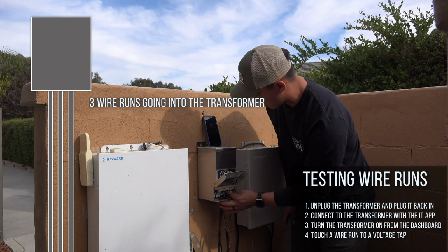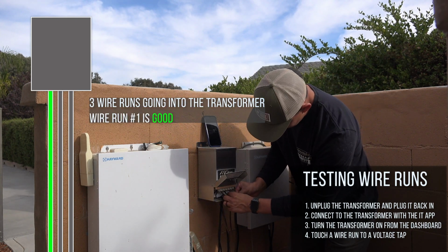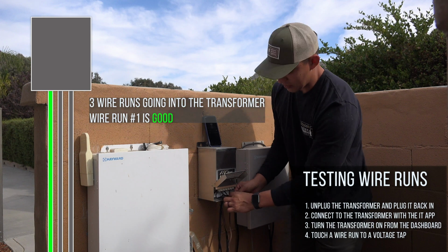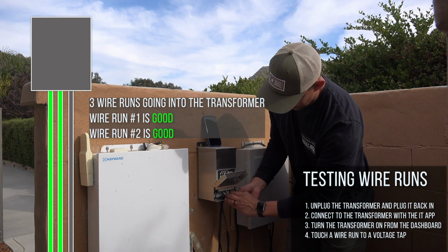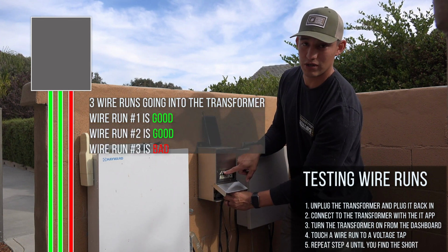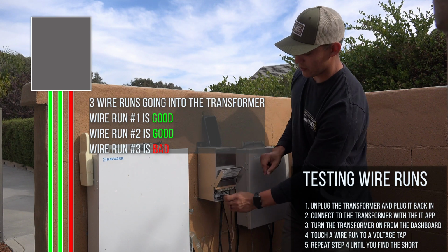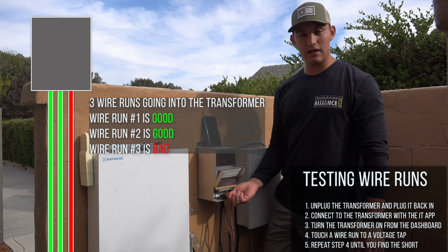Here we go, door number one, no trip. Number two, second wire run, did not trip the transformer. And my third wire run caused a fault on the transformer. So door number three, or wire number three, is causing an issue.